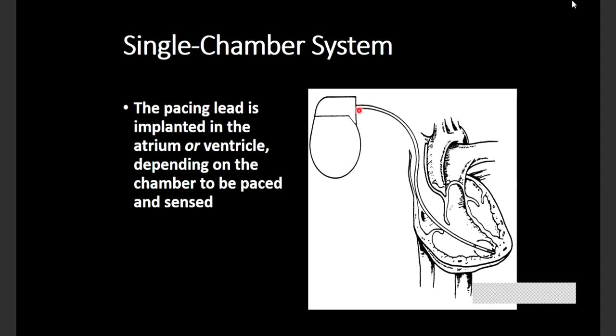The second reason would be if there's any problem with the lead. So if the lead gets displaced and doesn't touch the muscle, which is common immediately after implant in 1% of the cases, again, whatever current you're generating doesn't reach the muscle, because it's a displaced system. So unless it reaches the muscle, there is no capture. So the pacemaker system again fails.